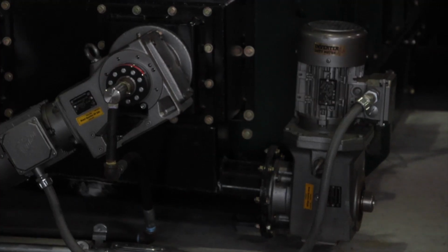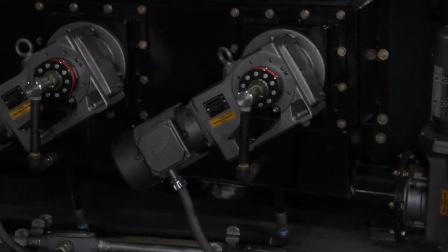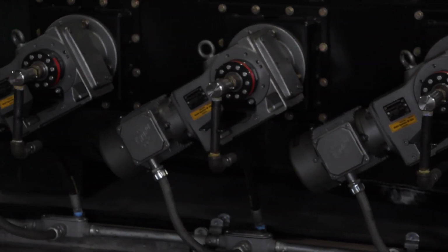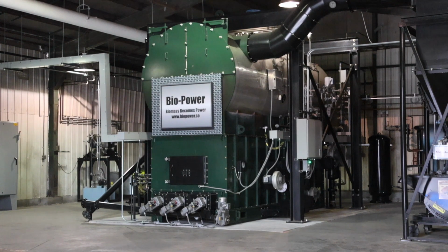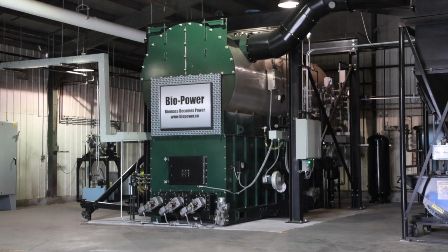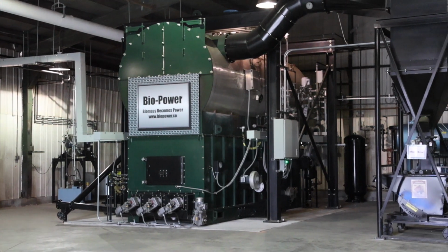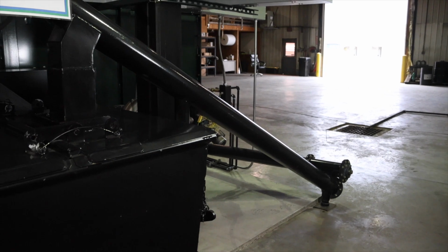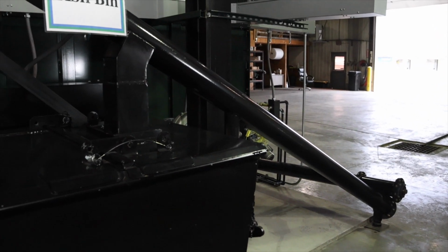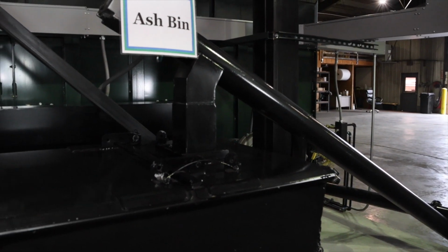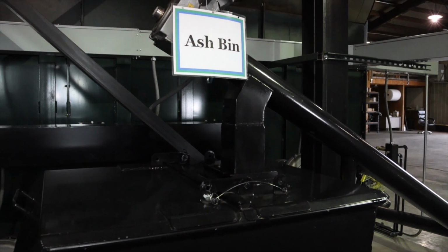These augers are water-cooled. The temperature is maintained by way of a circulating water cooling system. Water temperature and flow through the augers are monitored, greatly extending the operational life of the augers. The ash is collected in bins, which are periodically emptied.